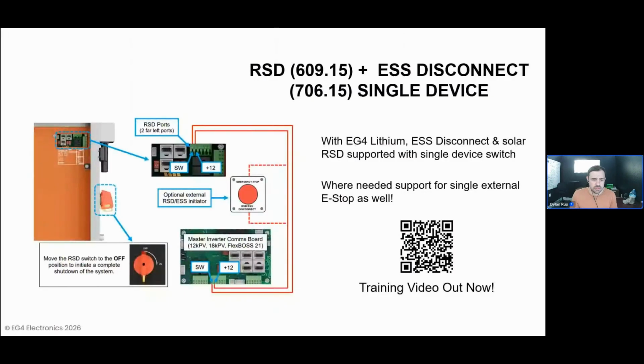The unit does support RSD and energy storage system disconnect with a single device. So if you are using the full EG4 product lineup, that disconnect and solar RSD can be supported by a single RSD button, right? So no matter what that AHJ wants to see as far as disconnect capability, you can generally meet it with a single device here, either by where you place the grid boss with the appropriate placards, or via an e-stop button that is deployed separately. That's a nice big red button for an emergency responder to see. We can put that e-stop capability where it's needed on site with as little equipment as necessary.